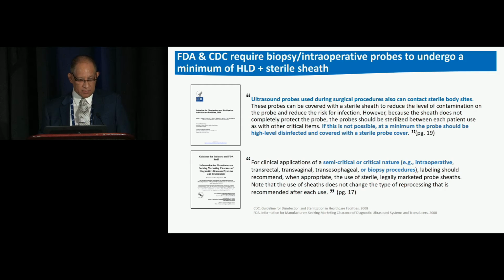If this is not possible, at a minimum, the probe should be high-level disinfected and covered with a sterile probe cover. And the FDA says the following: for clinical applications of a semi-critical or critical nature, for example intraoperative, transrectal, transvaginal, et cetera, labeling should recommend, when appropriate, the use of sterile, legally marketed probe sheaths. Note that the use of a sheath does not change the type of reprocessing that is recommended after each use. And why would that be?